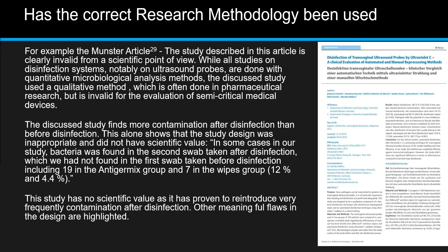In some cases in their study, they said bacteria were found in the second swab taken after disinfection which were not found in the first swab before disinfection. So this tells you that somehow in their methods, they're actually contaminating the probes. Certainly one could argue about how effective certain disinfectants or devices are, but you should never find higher numbers after disinfection than before, unless in your scientific method you're actually contaminating the device. So this study has fatal flaws.